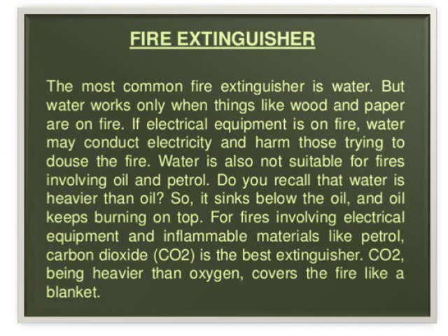Water is the best fire extinguisher when a fire has broken out in combustible materials like wood, paper, etc. But the same water cannot be used to extinguish fires that break out due to the leakage of current, as well as fires due to liquid fuels like petrol, kerosene, or even LPG.